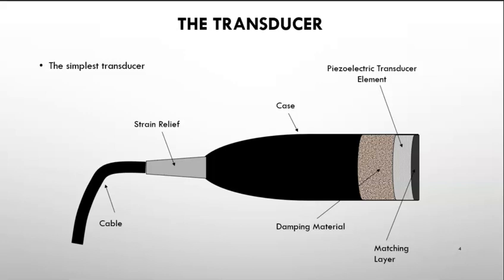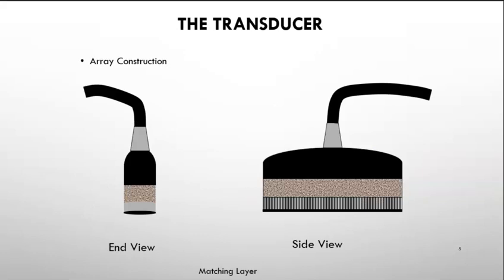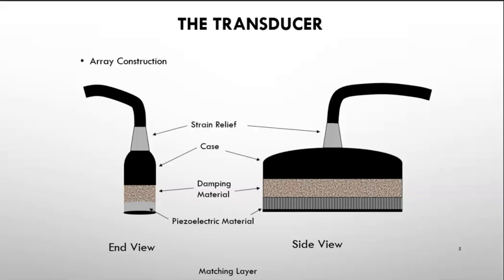So when we look at this transducer, we see the end-on view, and then we see a side view of the transducer where there are many small elements across the face of the transducer, and we'll talk about how those work in the future. And then you have this matching layer, damping material, case, strain relief, and cord. We will talk about why there are so many different crystals in the transducer in just a little bit here. So we have our piezoelectric material, again damping material, the case, strain relief, and cable, and then in the front is the matching layer.